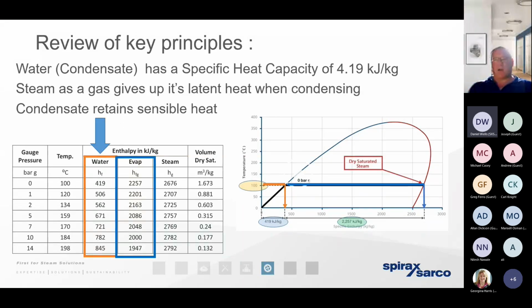And the harder the boiler has to work, the more fuel it has to burn, the greater the inefficiency and the more the carbon emissions. So we want to generate steam as dry as we possibly can in order to emphasize that efficiency. The other reason is if we've got any heat loss in the infrastructure, as the steam travels hundreds, maybe even thousands of meters around the infrastructure, as it passes across those condensate losses, the steam's going to degrade. So it's going to move further away from the dry saturated steam zone.